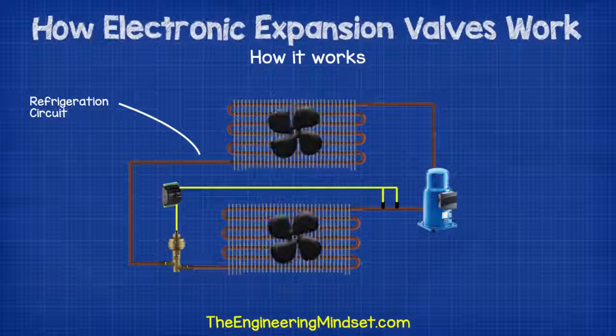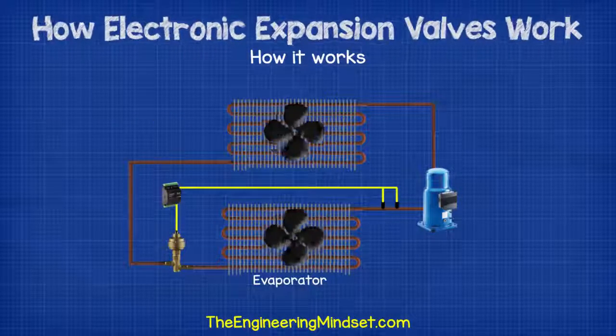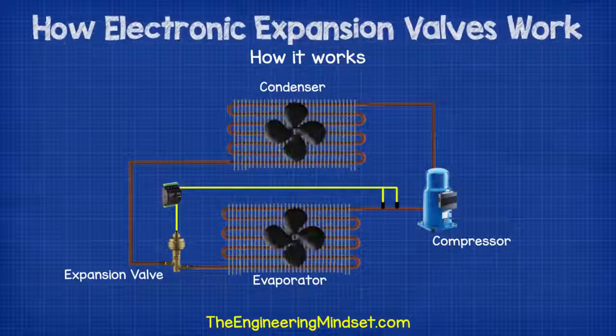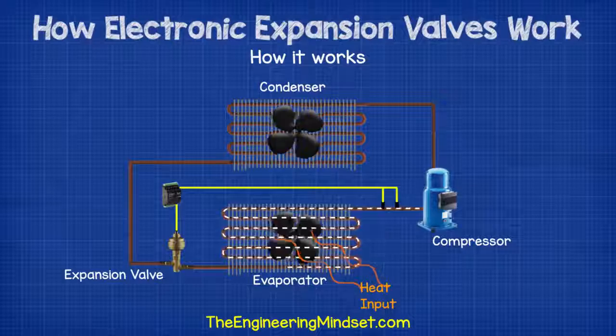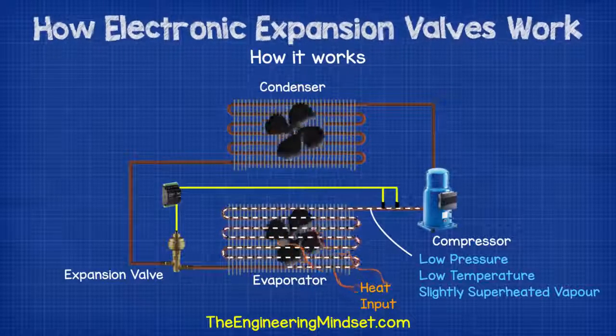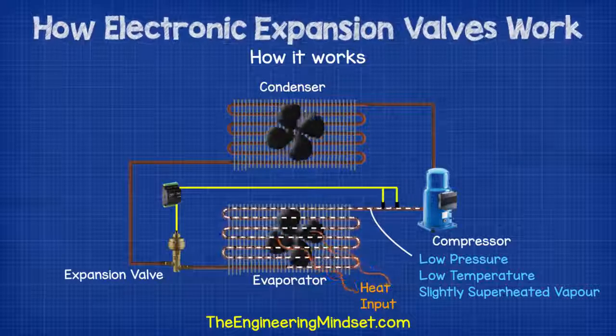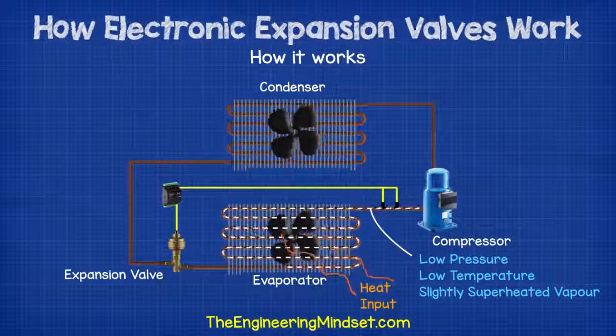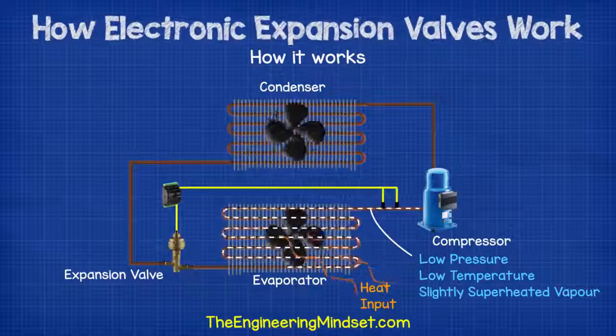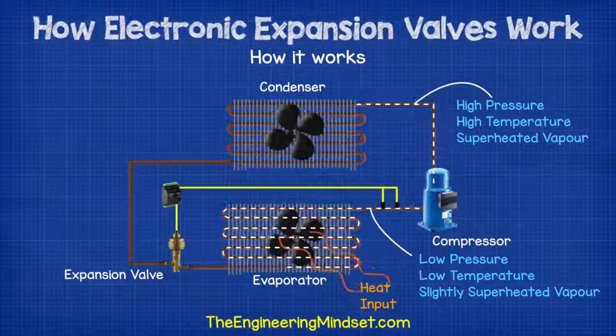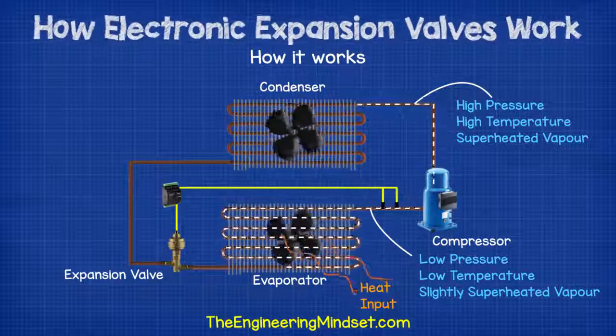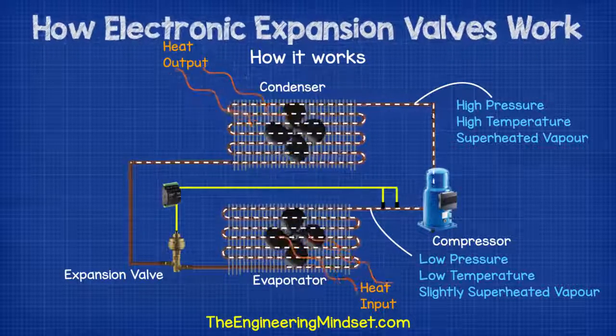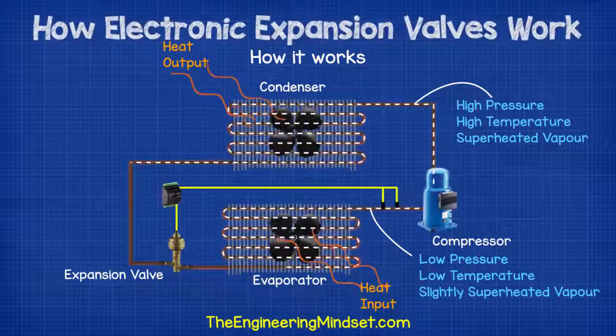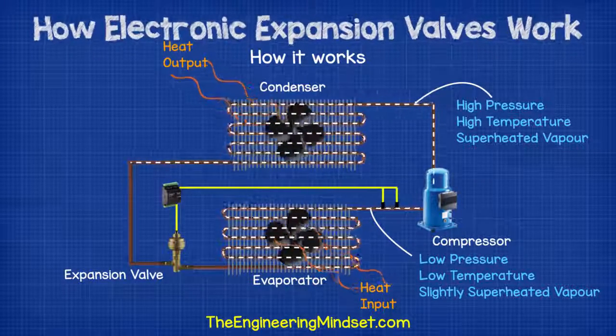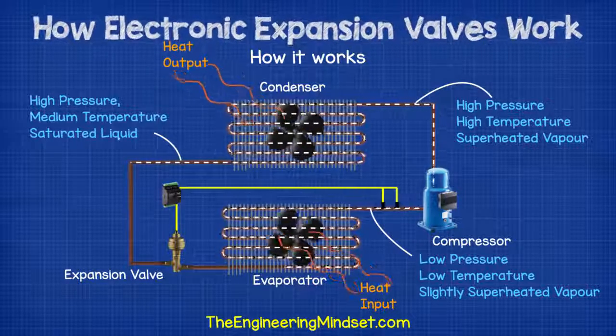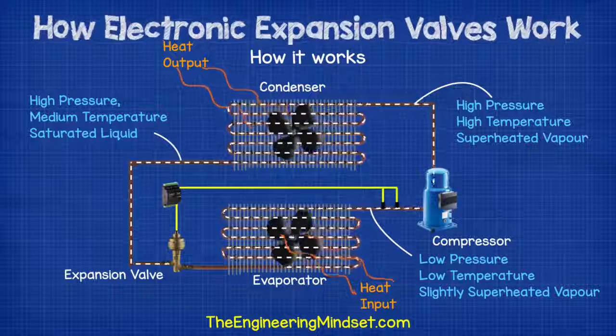So how does an electronic expansion valve work? If we have a look at a typical refrigeration system, you can see the main parts being the evaporator, the compressor, the condenser, and the expansion valve. The evaporator collects all the unwanted heat from the building and transfers this into the refrigerant, which causes the refrigerant to boil and evaporate. The compressor then sucks in this evaporated refrigerant, which is a low pressure, low temperature, and slightly superheated vapor. It then compresses this into a smaller volume, which causes it to be a high pressure, high temperature, superheated vapor. The refrigerant then moves to the condenser, where the unwanted heat is pulled out of the refrigerant and rejected into the atmosphere. This causes the refrigerant to condense into a liquid, so when it leaves the condenser, it will be a high pressure, medium temperature, saturated liquid.